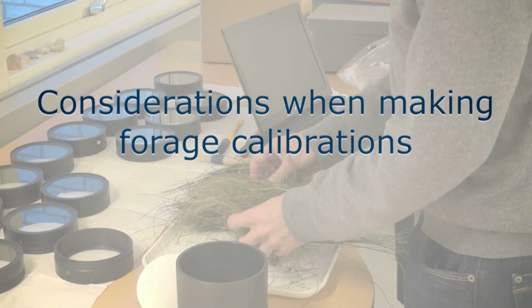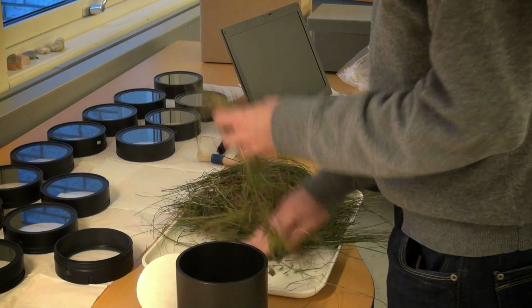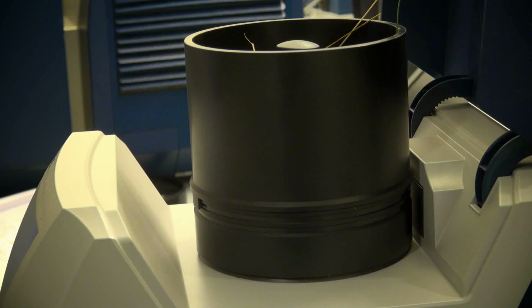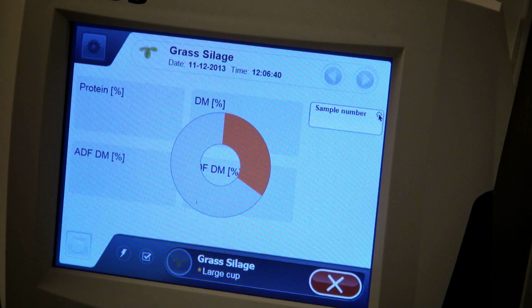There are some tricky things to keep in mind. The wet forage sample is very wet and changes its moisture content very quickly. As soon as you have measured your spectrum with the NIR instrument, it is important to take it to the reference analysis as quick as possible. That means practically that you take the sample from the sample cup and go start the pre-drying process.